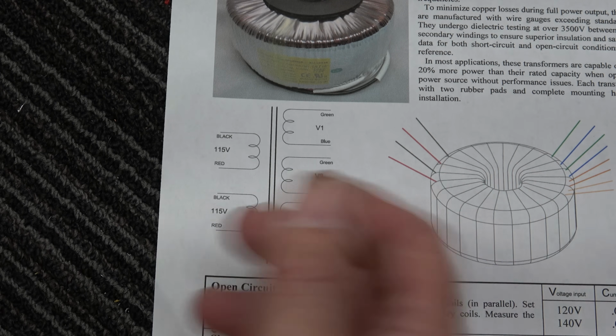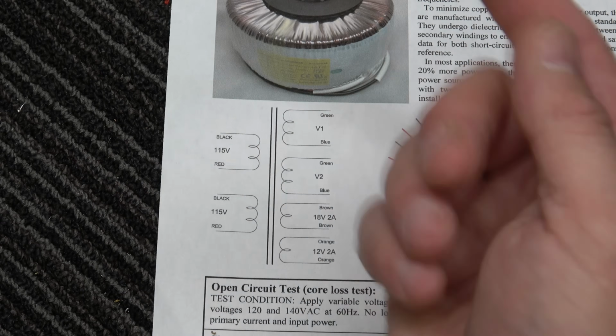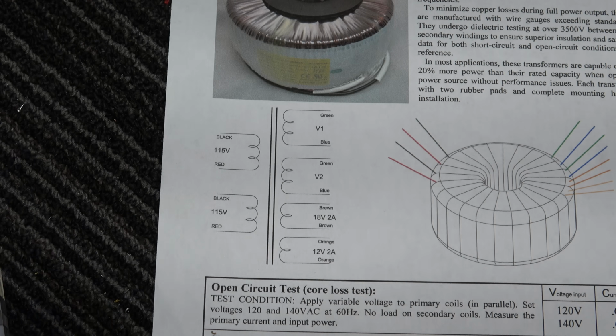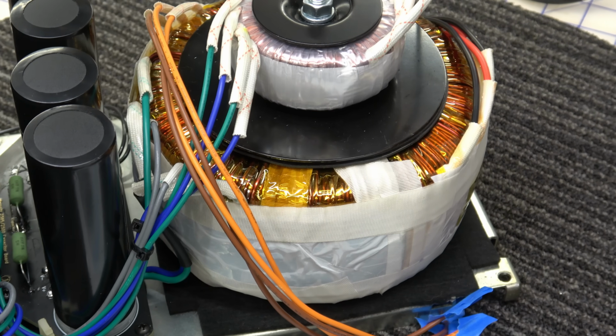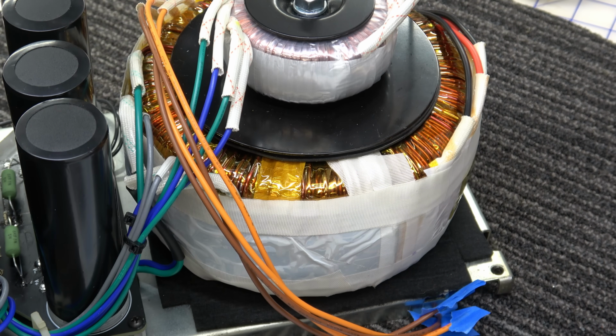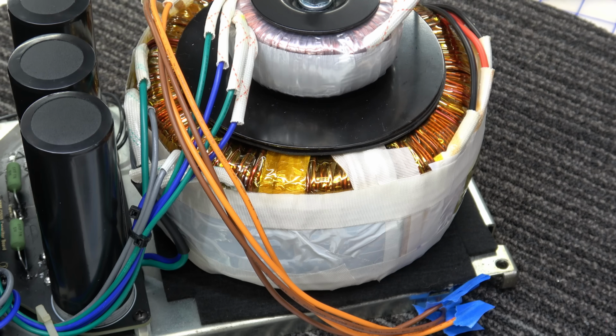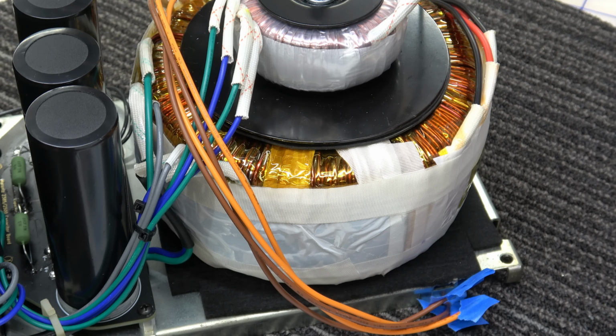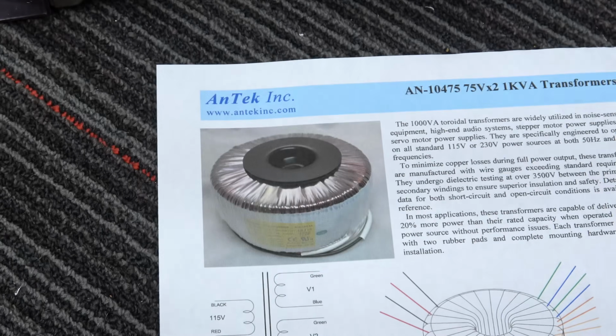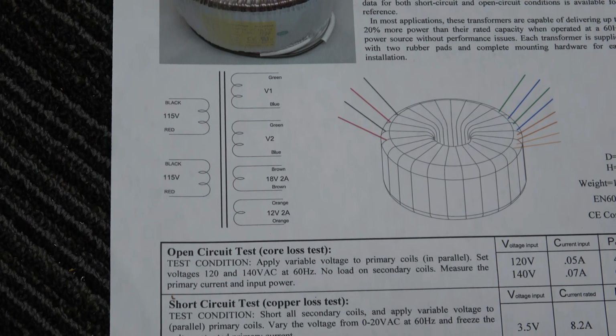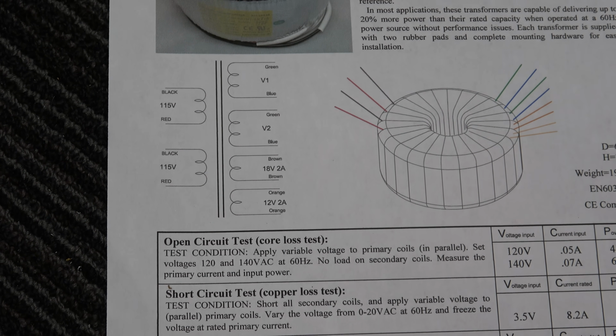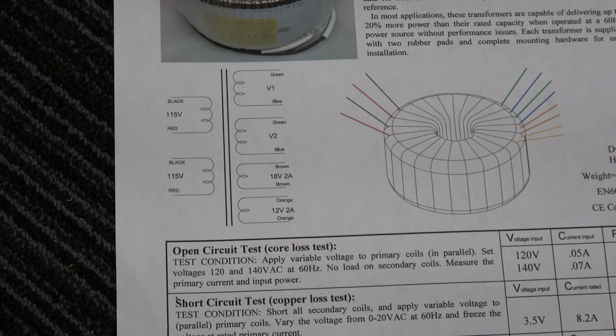The other thing is, if you're going to put a real heavy load on a secondary, whatever it turns out to be, you have to make sure the diameter of the wire used to wind that can handle that type of current. That's pretty thick wire they used on this, like number 16 gauge, I think, I don't know what that is in millimeters, but it can easily handle like 10 amps or so. So as long as we don't continuously draw more than 10 amps across this whole thing, you're going to be okay.